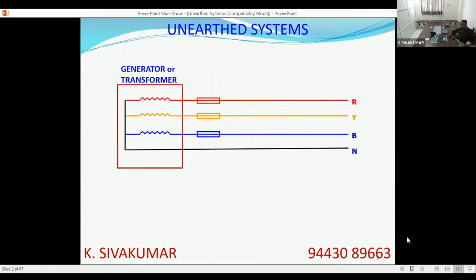The network will look something like this. The source may be a generator or a transformer, 3-phase 3-wire or 3-phase 4-wire. The distributed neutral may or may not be there, but the neutral is not connected to earth, either directly or through any impedance. It is not connected to earth. This will be the typical arrangement of the unearthed network.